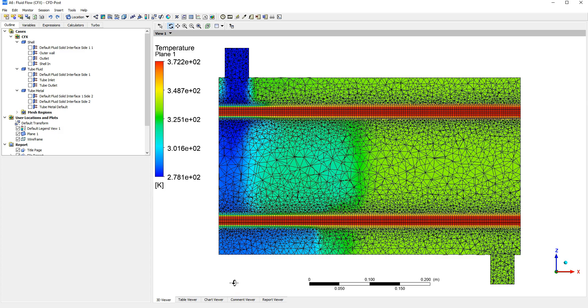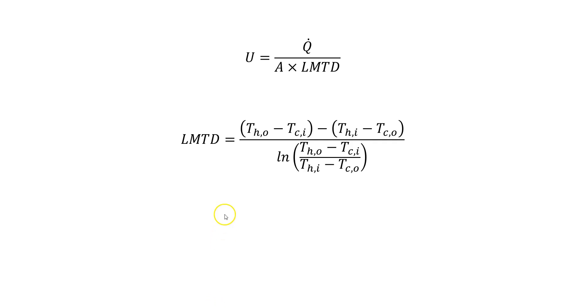If we begin by looking at the definition of the overall heat transfer coefficient: it is given by the variable U, where Q-dot is the rate of heat transferred out. That can also be written as mass flow rate times Cp times the change in temperature. A is just some area — in this case it's going to be the area of the outside of the tubes. There is also this LMTD term, which is the log mean temperature difference. It's an average temperature difference, but because heat transfer isn't linear along the shell and tube, we need to account for that by taking a log mean.